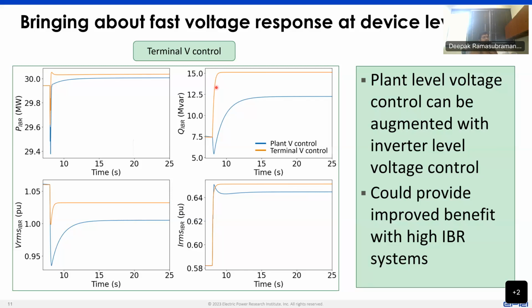Now, it can also be possible that some of the performance requirements that we define for close to steady state conditions can have an impact on the fault ride-through behavior, because they might end up being, so to speak, aggressive during the fault, which might then require specialized fault ride-through control to be enabled.